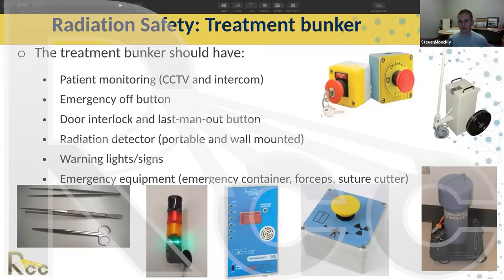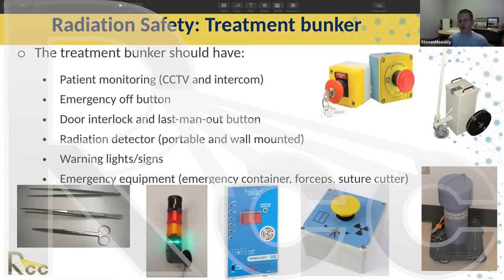The treatment bunker should have patient monitoring CCTV and intercom. In the United States, we aren't allowed to treat without audio or visual communication — that's a really good standard. You also need an emergency off button, tested daily, door interlocks, and a last man out button, though not all facilities are required to have one.